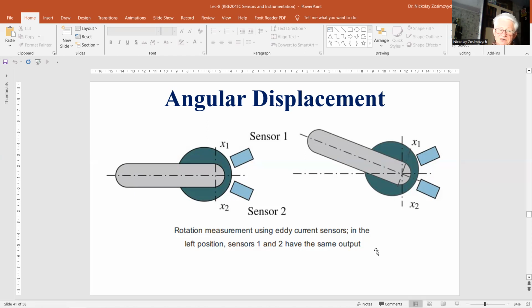An interface circuit converts a change in inductance due to a passing tooth of a gear wheel to a frequency change from 9 to 11.6 megahertz. And this sensor also allows analog distance measurements with 50 nanometer resolution over a half millimeter range. Although the working range of eddy current sensors is limited, the measurement range can be enlarged by mechanical reduction of the movement to be measured.